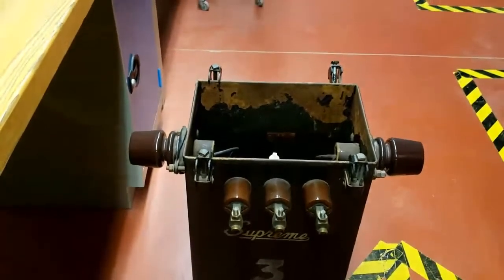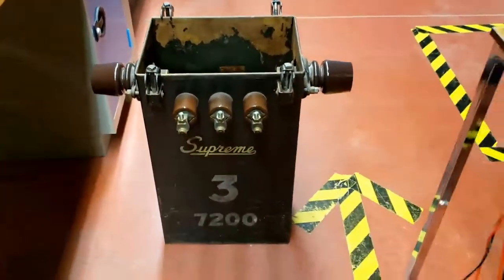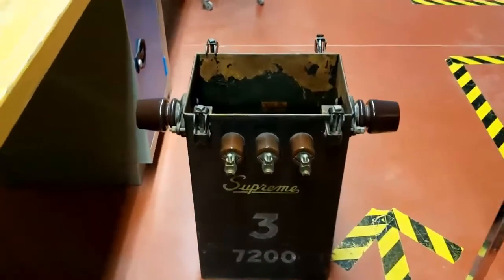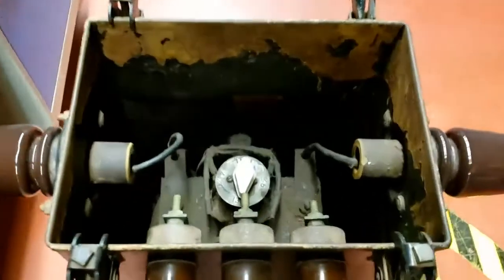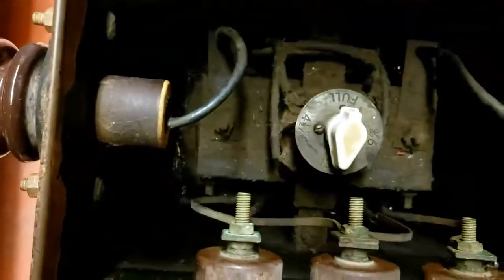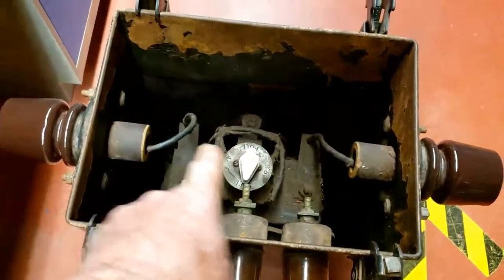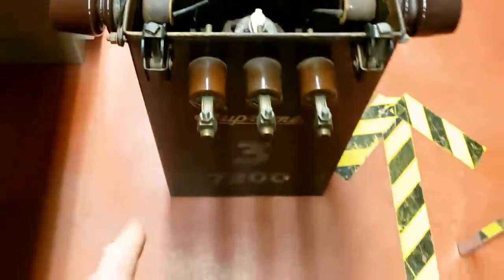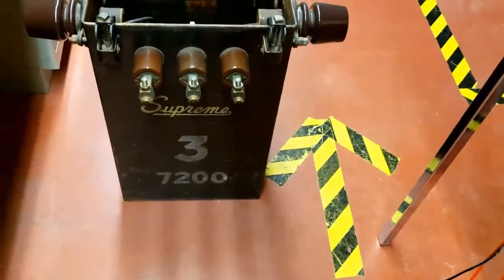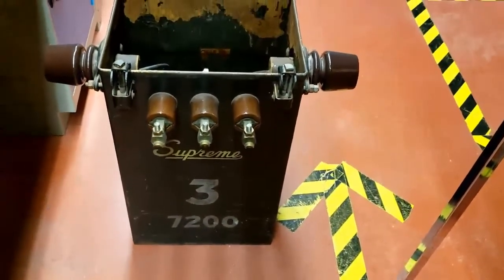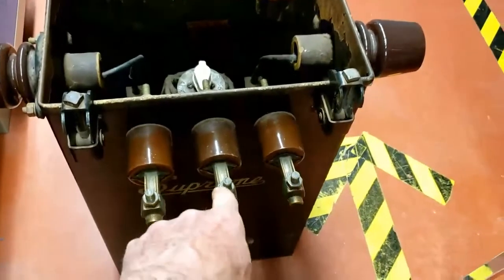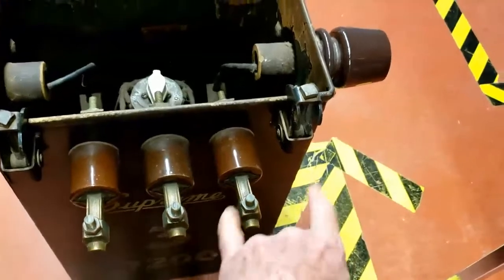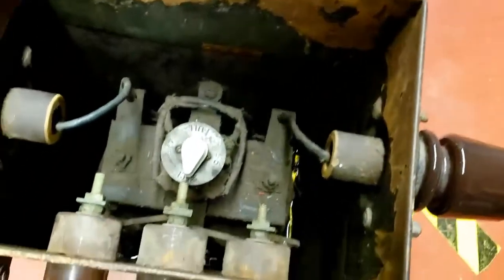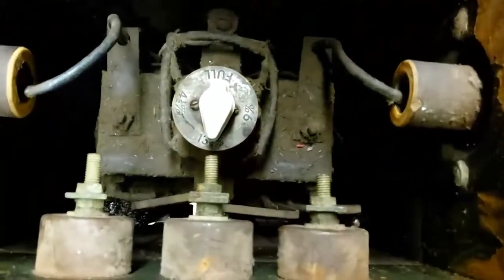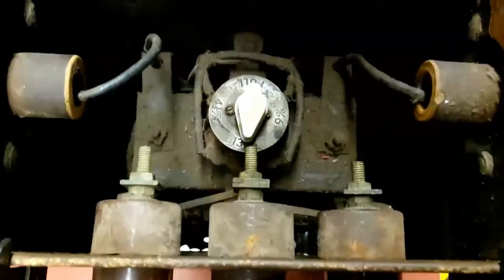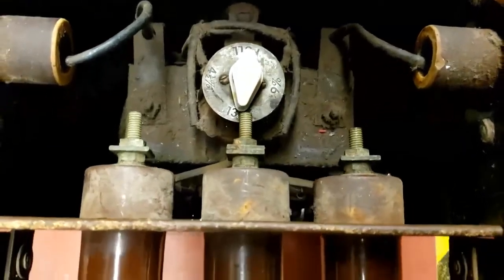Lab 1 is the pole-top transformer insulation testing. This is a very old model of the pole-top transformers, and inside is a transformer. It's got the two high voltage terminals here, and it has the low voltage terminals. So this is 7200 volts primary. So secondary for residential is 240 volts with a center tap, which is our neutral, so we get 120 and 120. Inside also has a tap changer. You can boost the voltage either 4%, 9%, or 13.5%.